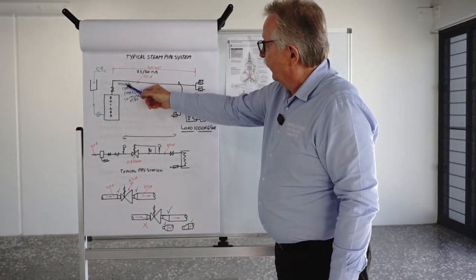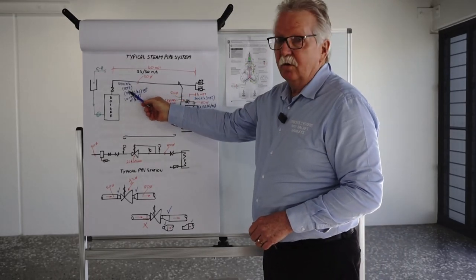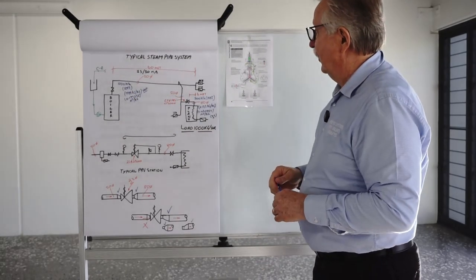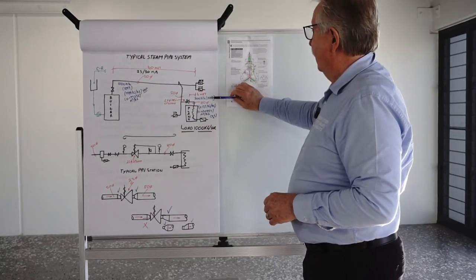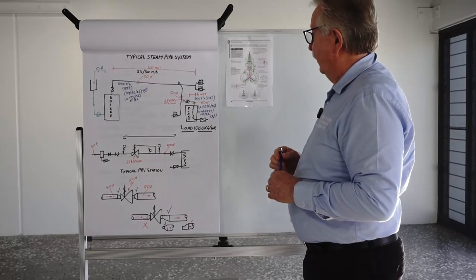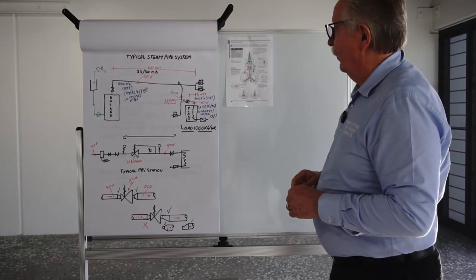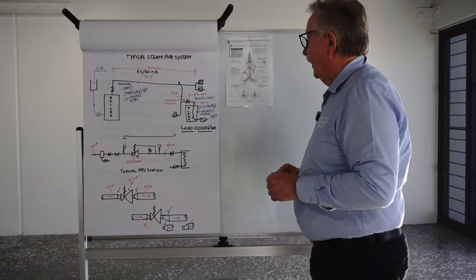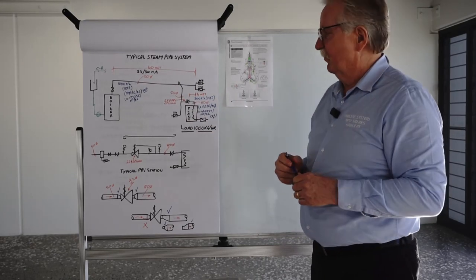In this case 1000 kPa steam is 184 degrees C. If you look at your steam tables you can verify that. 300 kPa steam pressure is 144 degrees C. So there's a 40 degrees C difference between the 1000 kPa and the 300 kPa. So that's a couple of reasons why you might pressure reduce.